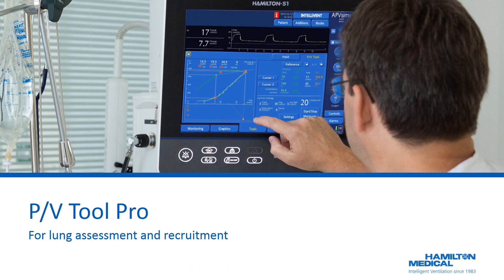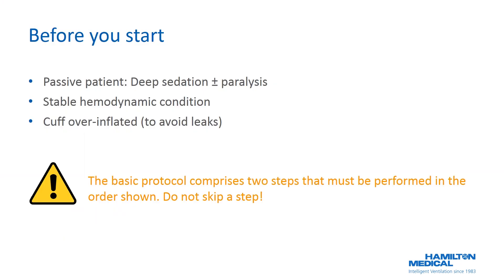We will now discuss the utilization of the PVTool Pro option. Most patients require deep sedation, with some patients requiring an additional neuromuscular blockade to prevent spontaneous breathing efforts. Monitoring the patient's hemodynamics during both the diagnostic and recruitment maneuvers is crucial. In the event of any hemodynamic impairment, stop the maneuver immediately. Ensure the ET tube cuff is inflated to a pressure higher than the maximum pressure specified in the PVTool settings. If used, the IntelliCuff pressure controller automatically adjusts the cuff pressure accordingly.